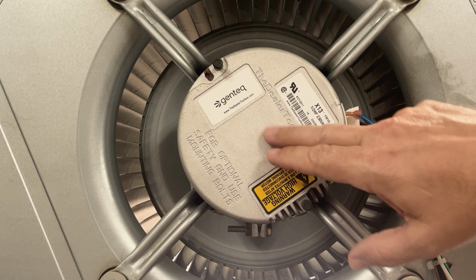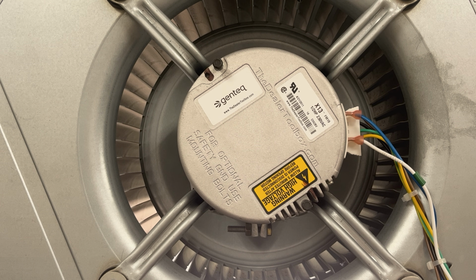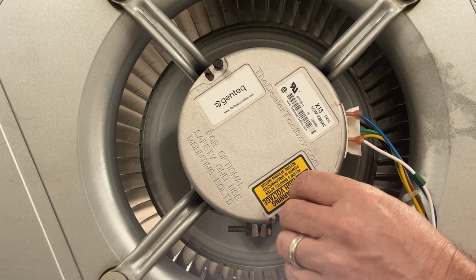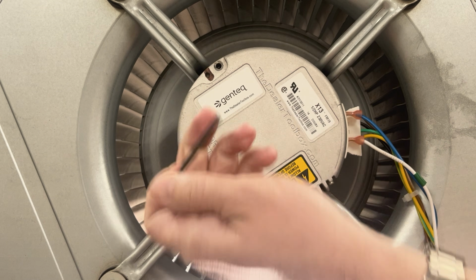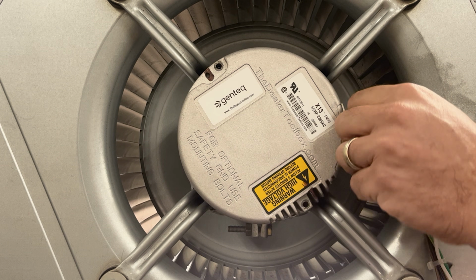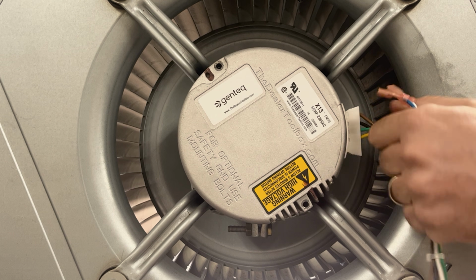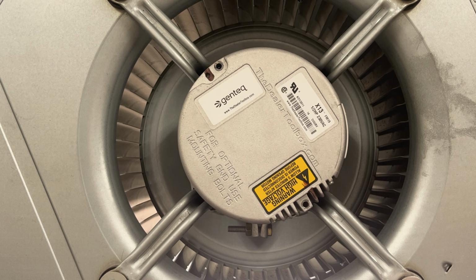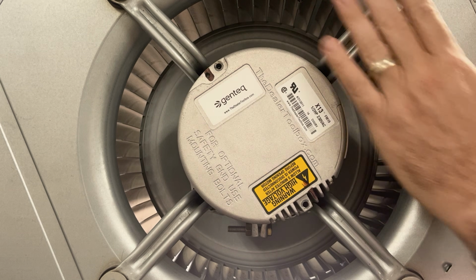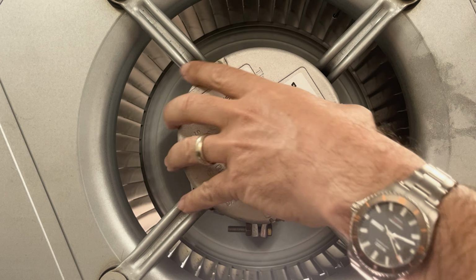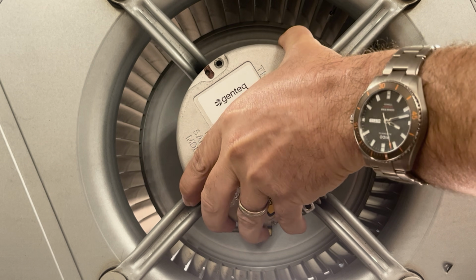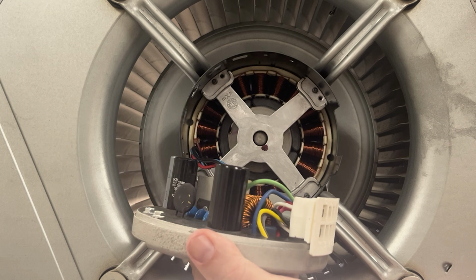Now remember, there's a relay in here, so the only way I can test if the motor has an open winding or if the windings are good, it's called the brake test. I would have to remove this module completely off of here. So I already got the screws loose. So I'm gonna pull these screws out, and I'm gonna go ahead and unplug all the factory wires. And I don't have to remove the motor from the blower wheel, because I'm actually gonna use the blower wheel as my tool.